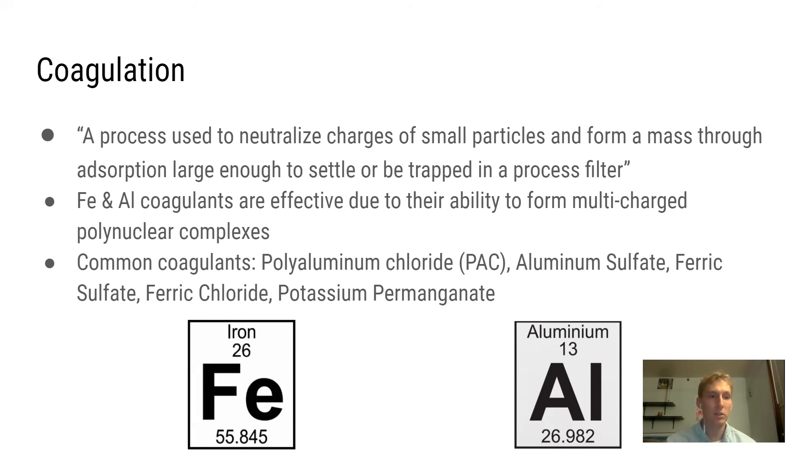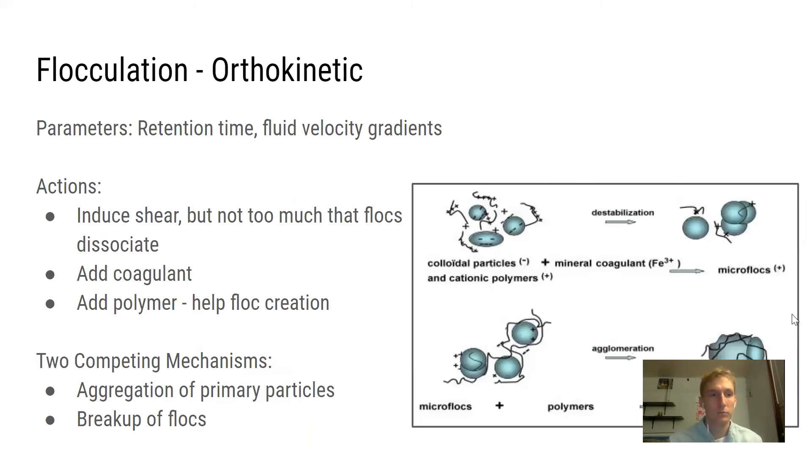The most common coagulants you'll see are PAC (polyaluminum chloride), aluminum sulfates, iron sulfates, iron chloride, and potassium permanganate is also fairly common. Next we get to flocculation, which is very closely related to coagulation. When people talk about flocculation, they mainly talk about forming those larger flocs in a very similar way as coagulants do. It is called flocculation literally because these flocs form and then usually can settle out of the water similar to sedimentation process, but it is from an added chemical that is able to react with the particles that are water soluble.